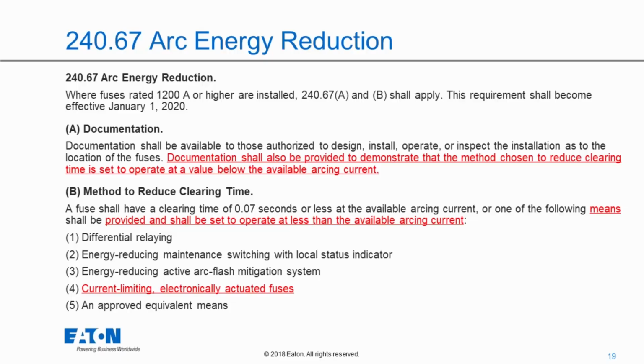Also note that since we're in Article 240, this applies not only to service disconnects, but any overcurrent device, any fuse rated 1,200 amps or higher. Could be a feeder. It could be a feeder off of an alternate source of power. So any fuses need to be addressed. And I want to caution you, sometimes people would say, well, what if I had a 3,000 amp main with a 1,200 amp feeder? If I put arc energy reduction technology on the 3,000 amp main, does that then cover the 1,200 amp? And the answer to that is, the way it's worded right now, the answer is no. You'd have to look at each of them separately.